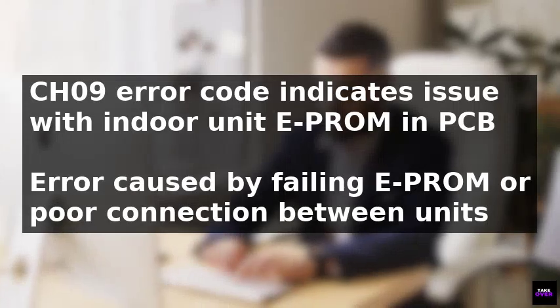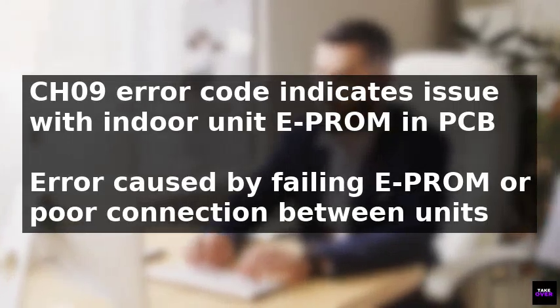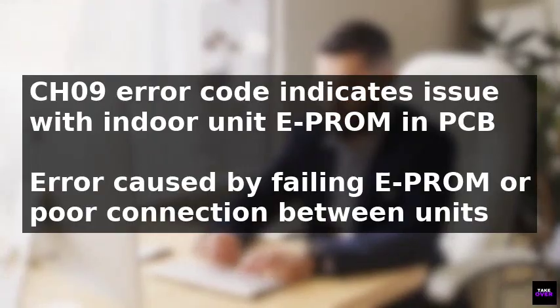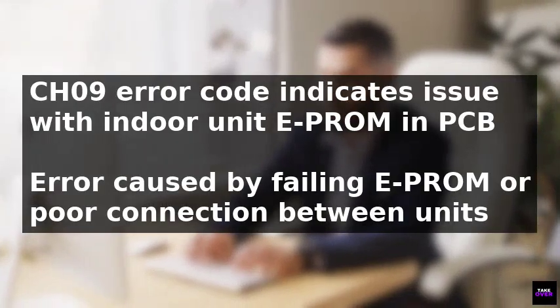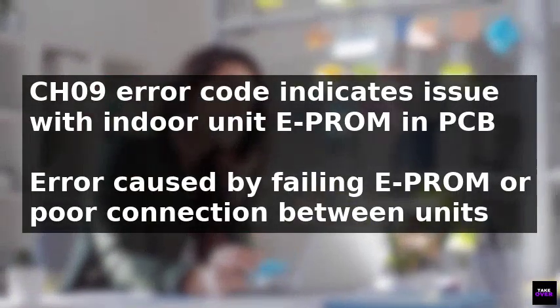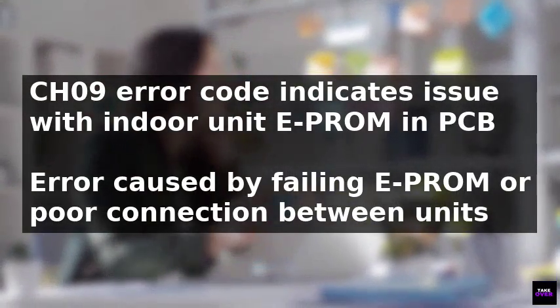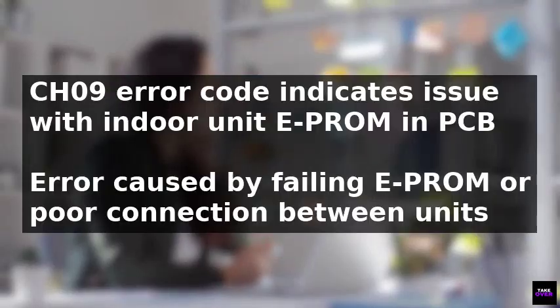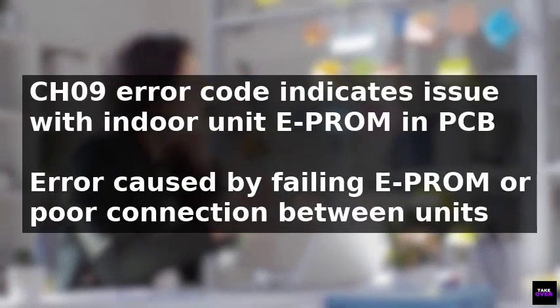The CH09 error code on an LG air conditioner indicates an issue with the indoor unit's EEPROM in the PCB. This error can be caused by a failing EEPROM or a poor connection between the outdoor and indoor units.